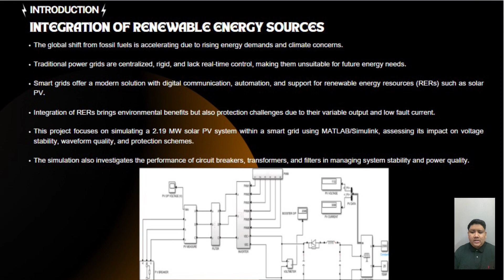However, integrating renewables brings new challenges. Solar energy is intermittent and produces lower fault current, which can affect the performance of protection systems. In our project, we simulate a 2.19 megawatt solar PV system within a smart grid using MATLAB/Simulink to study how it affects voltage stability, waveform quality, and protection coordination.